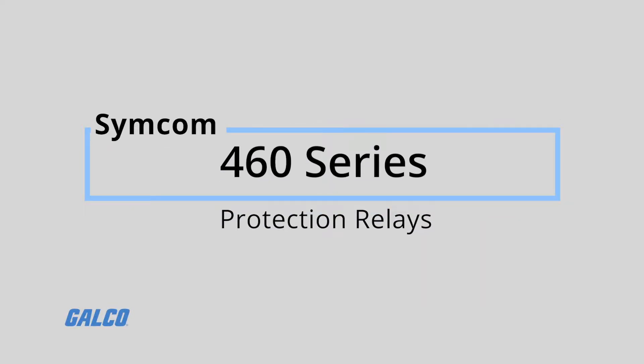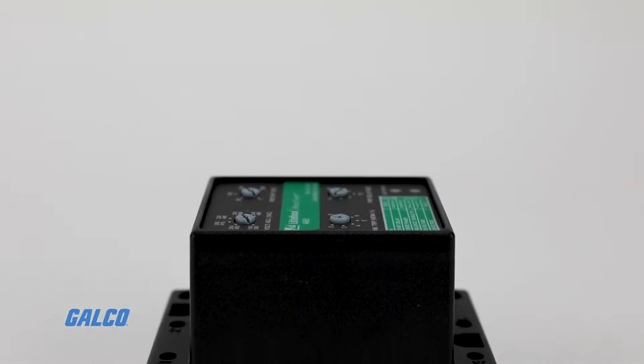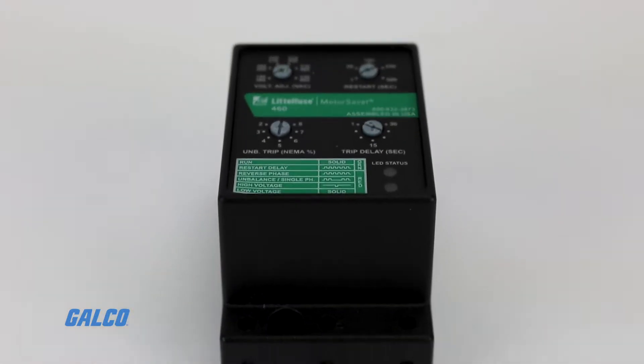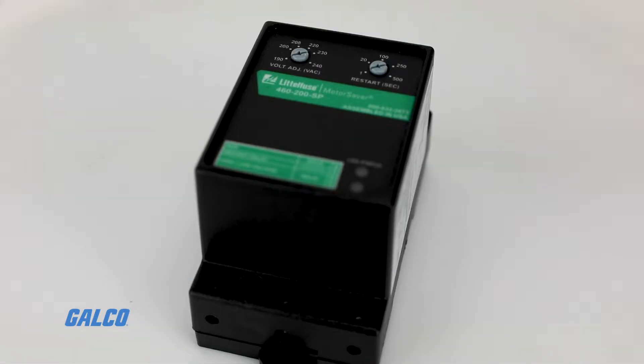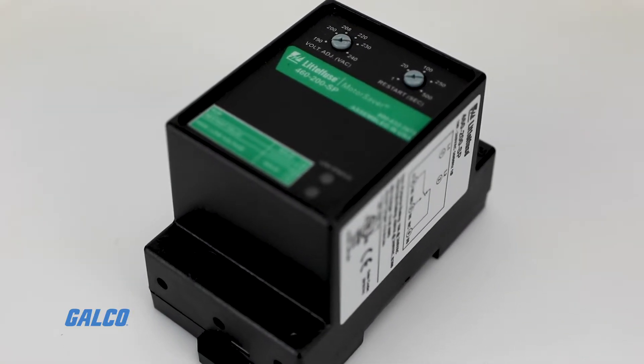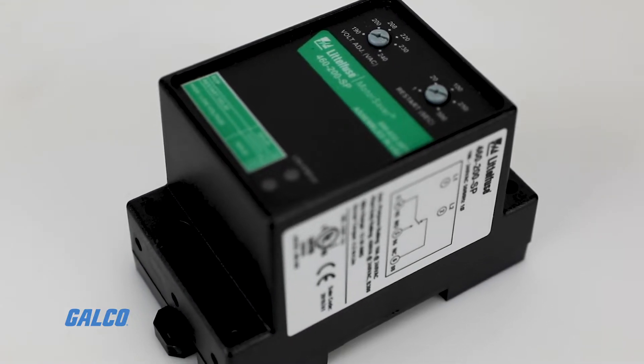Symcom's 460 Series Protection Relay is a three-phase voltage monitor that protects 190 to 480 or 475 to 600 VAC motors, regardless of size. The 460 Relay is microprocessor-based, with voltage and phase sensing to constantly monitor three-phase voltage to detect harmful line conditions.